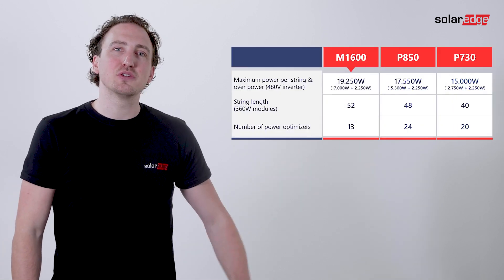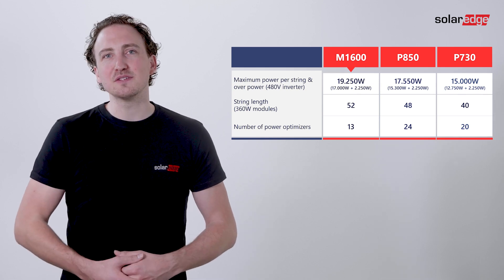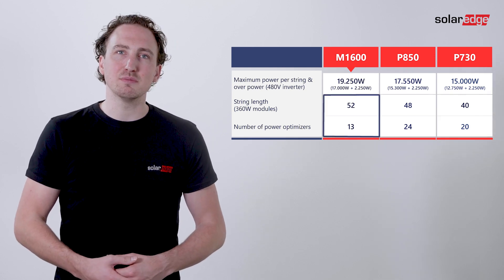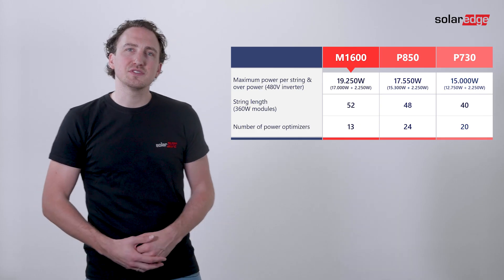To illustrate how the M1600 offers more power per string, let's compare it to the commercial P850 and P730 power optimizers. When connecting to a system comprised of 360 watt peak modules, notice how the string length as well as the maximum power per string varies between the models. Focusing on the M1600, we see how it allows significantly longer strings up to 17,000 watts and significantly fewer optimizers per string, thanks to the 4-to-1 module to power optimizer ratio.